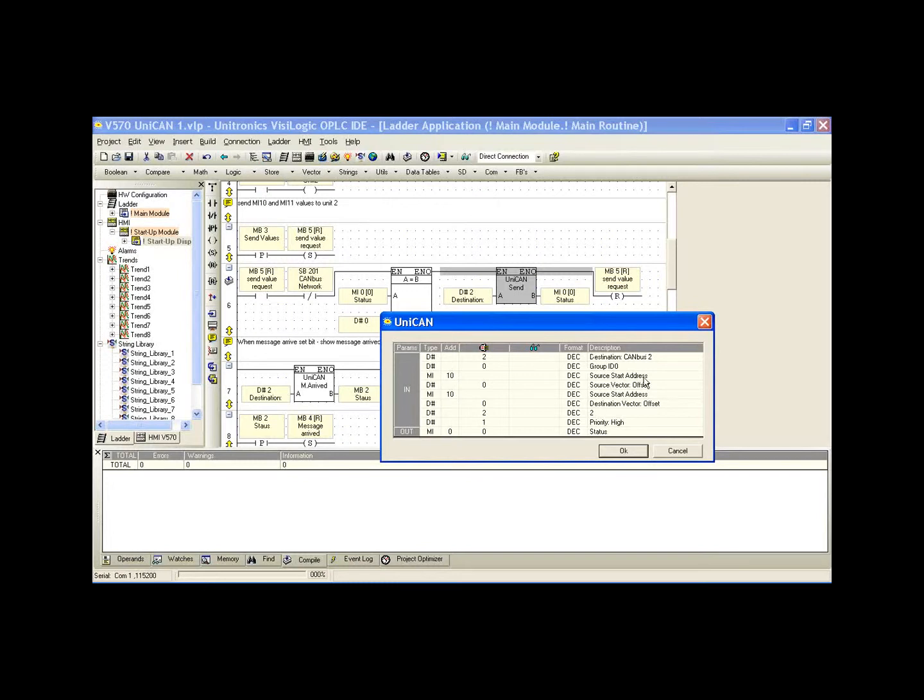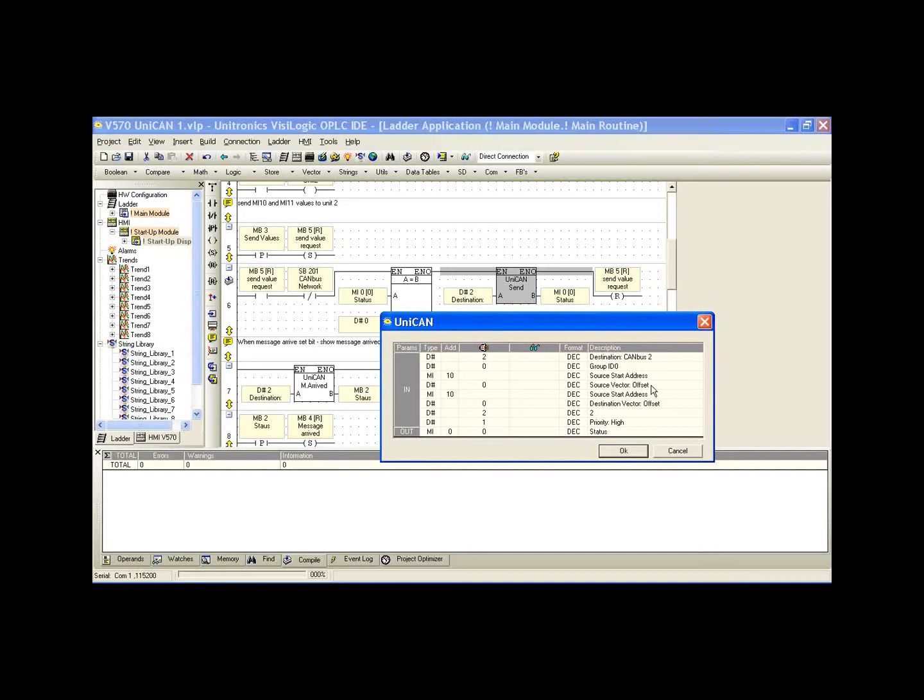The source start address, in this case MI10, remember we're sending memory integer 10 to controller 2, where we're sending 10 and 11. MI10 is our source address. This is the address in our master controller that's sending to our slave controller. The source vector offset, we could use the offset if we wanted to offset based on MI10, meaning if I selected the value of 1 here, we would send MI11. If I selected the value of 2, we would send MI12. This can be useful for indirect addressing. If we want to create a scheme that's going to send MI10 and 11 and 12 and then 13, we can use this in that manner. Also, if we simply have different local addresses for information, we can just jump between them using the offset.